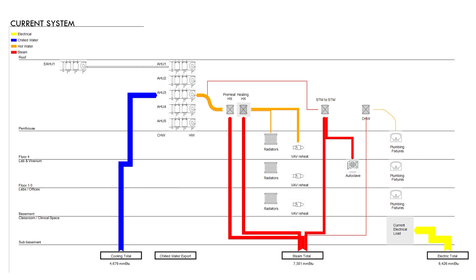After the conversion, this is what it kind of looked like. We went ahead with a 210-ton heat pump. It's going to serve all the hot water needs for the building, and most of the chilled water. We still have to supplement off the district chilled water loop.